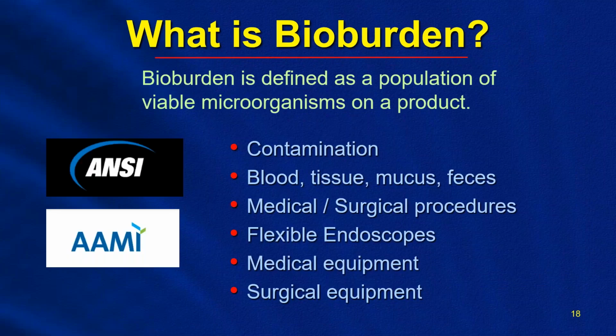So we talked about bioburden on instruments. So what is bioburden? Well, according to ANSI and AAMI, a bioburden is defined as a population of viable microorganisms on a device or a surface. Bioburden can result from the contamination by, again, blood, tissue, feces, mucus. It can be found on medical and surgical equipment and endoscopes after they have been used on patients in surgical and procedural areas, as well as the surfaces in these surgical and procedural areas. Now, this gross contamination, if left on surfaces or in scopes and instruments for too long, may allow for the formation of biofilm.